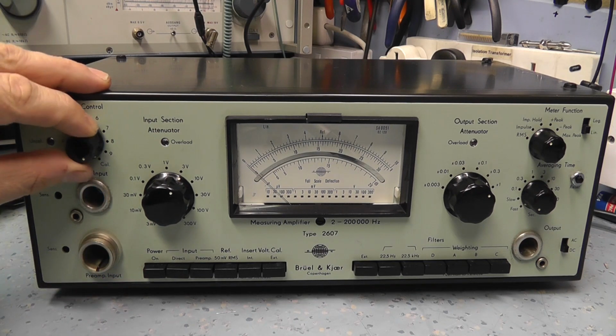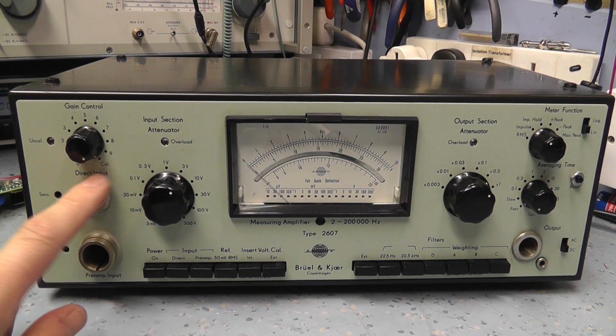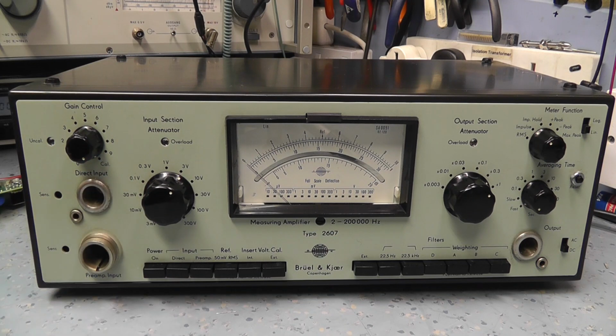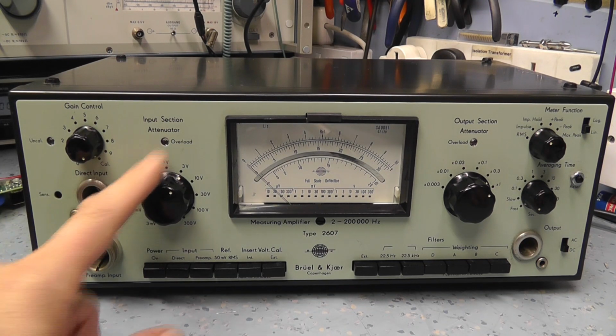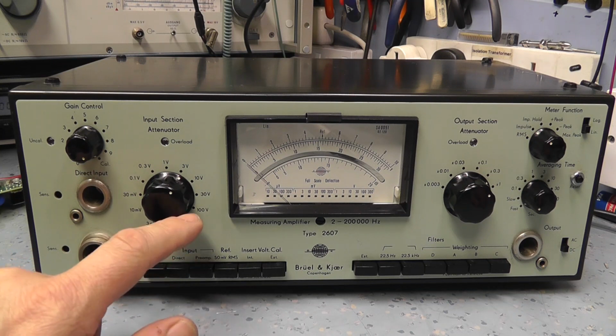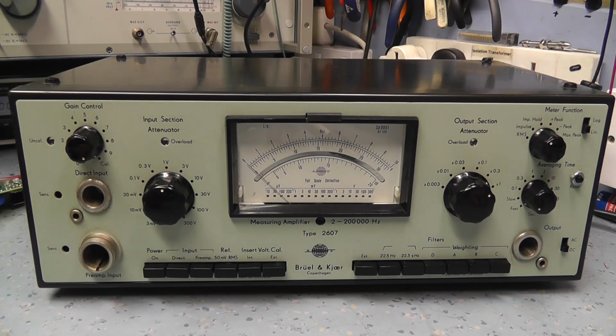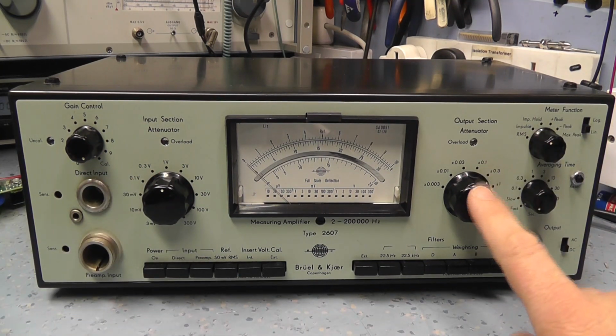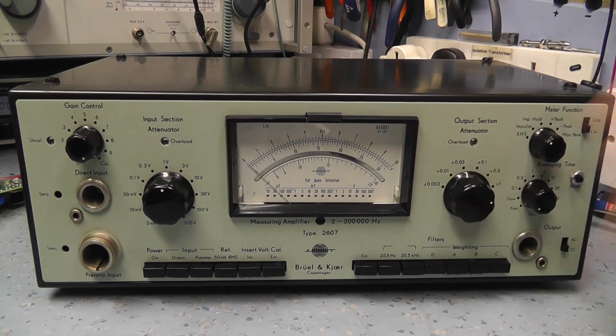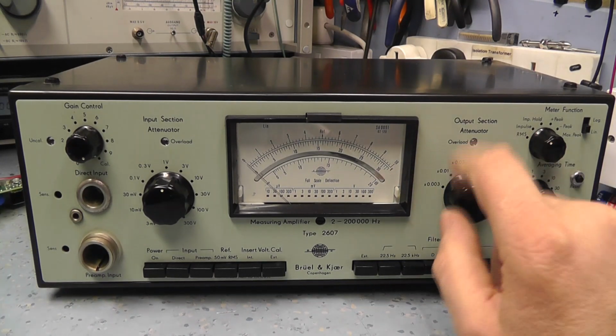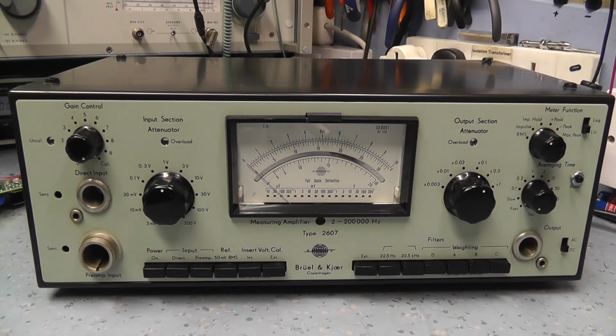Then we've got gain control, which is basically you set that to calibration mode for scale accuracy. And this is our input attenuator, as you can clearly see is marked here. And then you select your input range here, and on the right hand side here your multiplier. So if you want 3 volts, obviously you put it times 1. If you want 300 millivolts, you put it times 0.1.